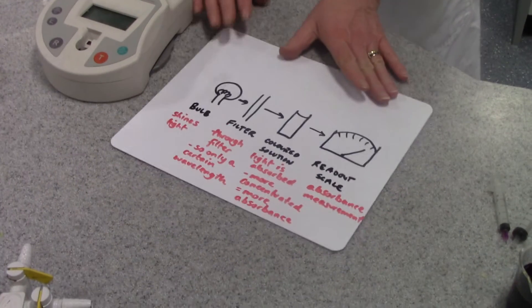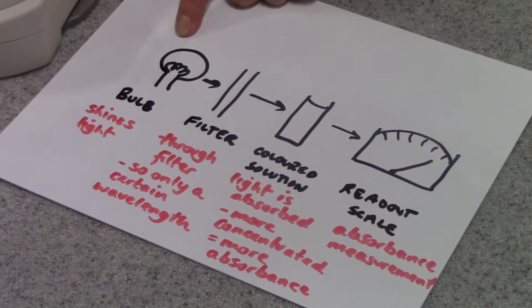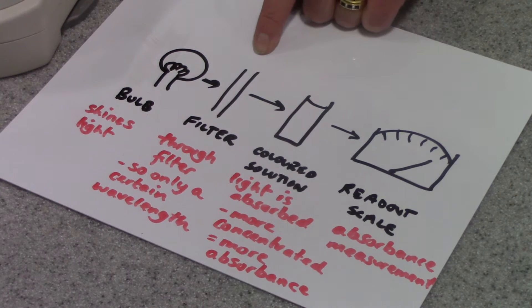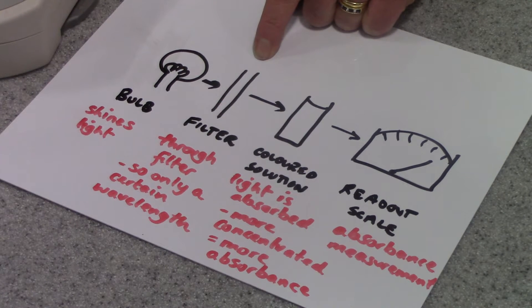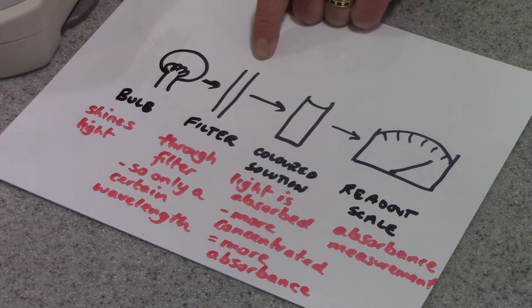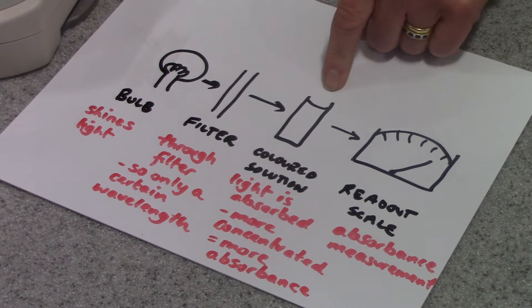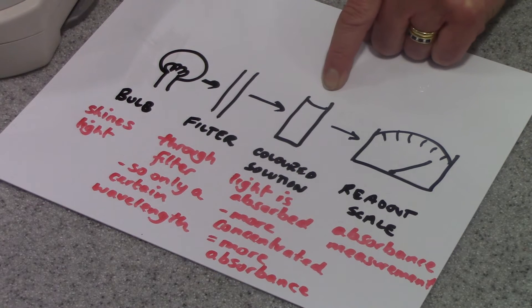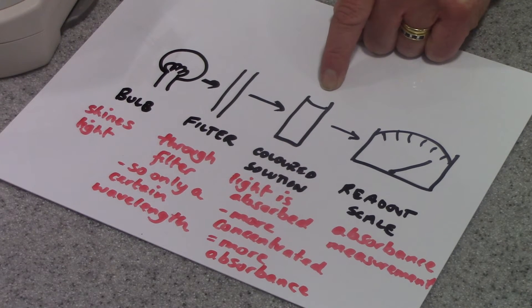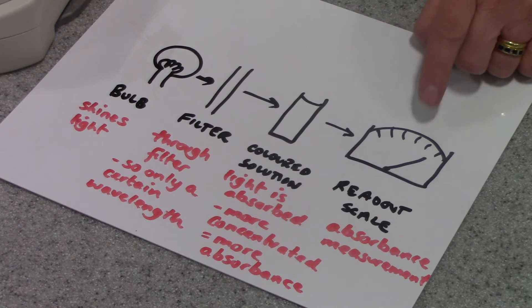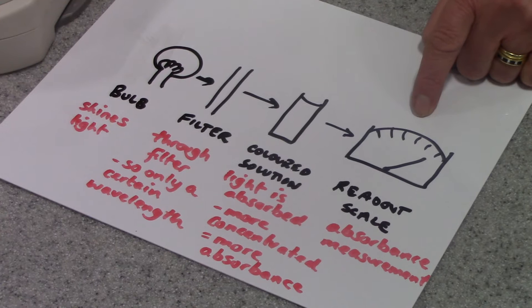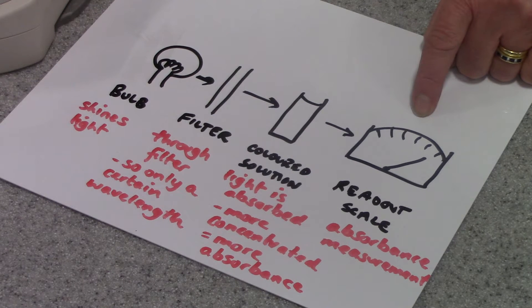If we look inside a colorimeter, we can see that there's a light bulb and this shines a light through a colored filter. This filter only allows light of a certain wavelength to pass through. The light then passes through a colored solution that you wish to determine the concentration of. And then a readout meter gives you a numerical value for the amount of light absorbed.